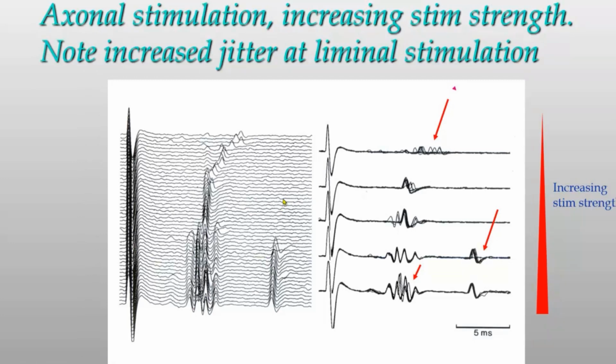There is a problem with the electrical stimulation, namely at borderline stimulation we get both long latency and signal jitter and blocking that takes place in the point of stimulation. And therefore we increase the stimulus just a little, from maybe 3 milliamp to 4 milliamp, and then it becomes all of a sudden more stable and does not decrease in jitter more with increasing stimulus. If we increase it a little more because we are uncertain about if it is supraliminal or not, then a new muscle fiber is coming in because we stimulated a neighboring nerve twig, and that comes in with an increased jitter, so we cannot use that for measurements.